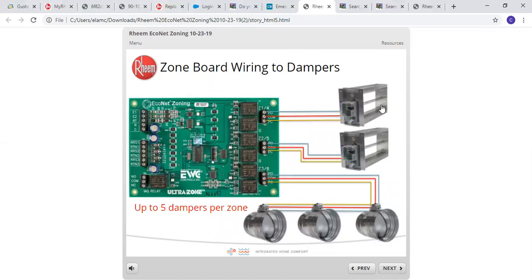So as you can see here, in this case you've got 3 zones. 1, 2, 3, power open, power closed, common. And on the bottom here, you can go up to 5 zones. In this case, you're going to daisy chain them all in. 1, 2, 3, and home run it back to, in this case, zone 3 or 6 on the panel.